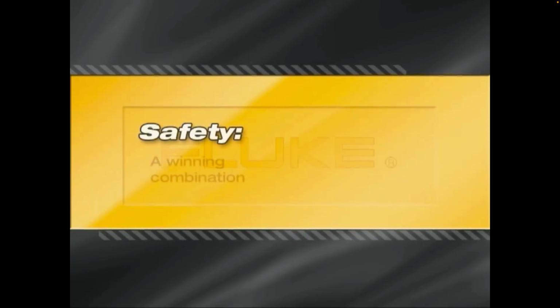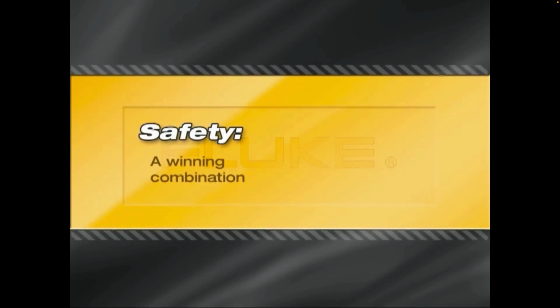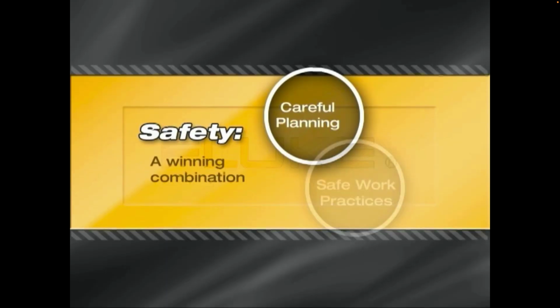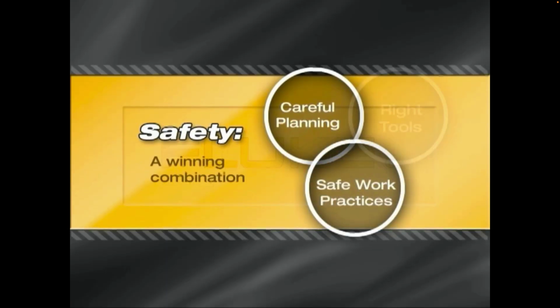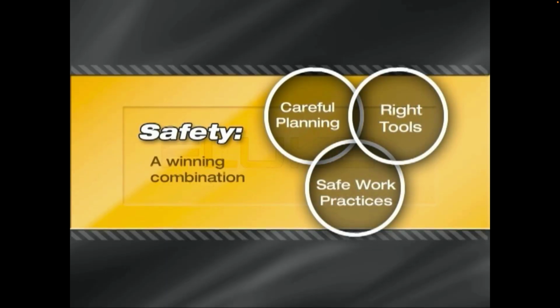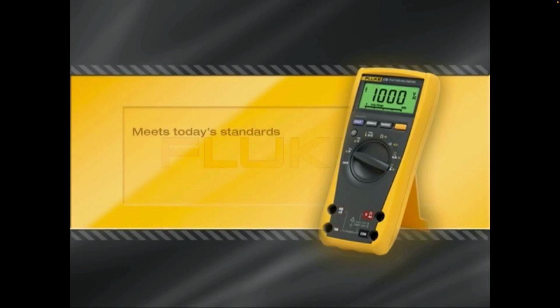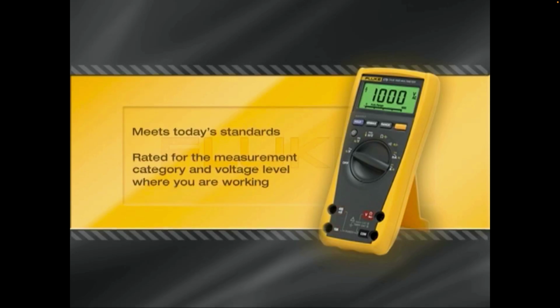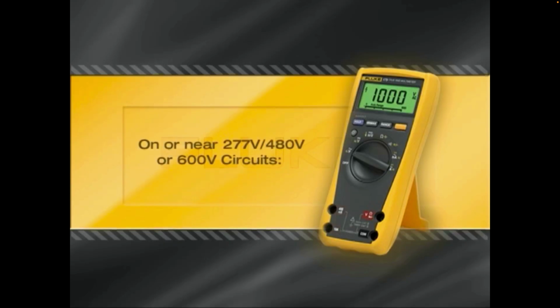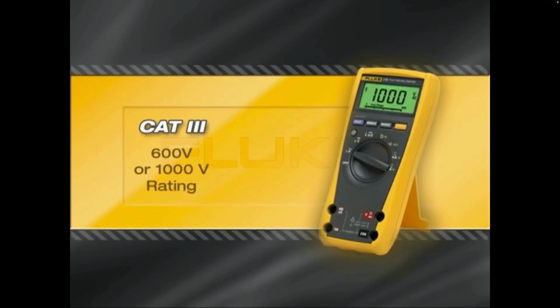Safety is the result of a winning combination. Careful planning and the correct safe work practices combined with the right tools. Use a meter that both meets today's standards and is rated for the measurement category and voltage level where you are working. If you use test equipment on or near 480 or 600 volt circuits, you should use 600 or 1000 volt Cat3 or 600 volt Cat4 meters and testers.